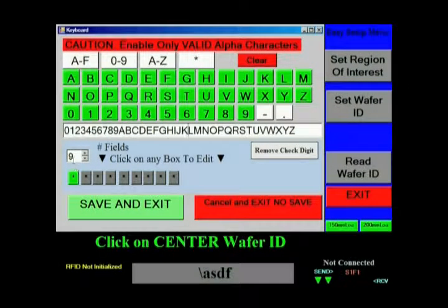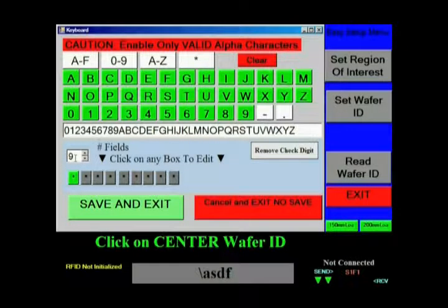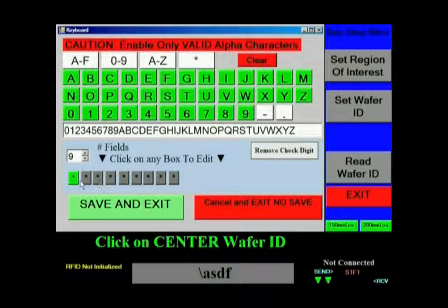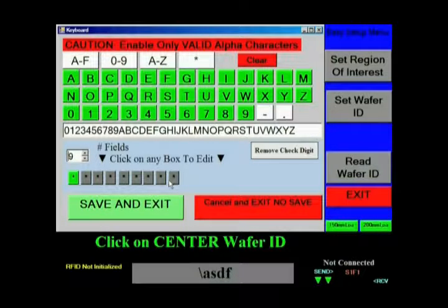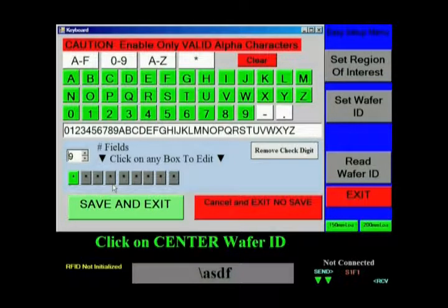This next screen is where you'll set the wafer ID. Right now, the software is set to read a nine-digit barcode. Each of the shaded boxes that indicate one of those digits now holds a star. That star means that the computer will assume that each of the digits can be any character — 0 through 9, A through Z. This gives you the widest range possible when reading your wafer ID.